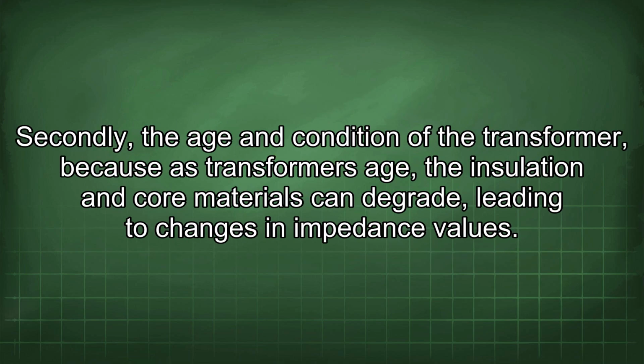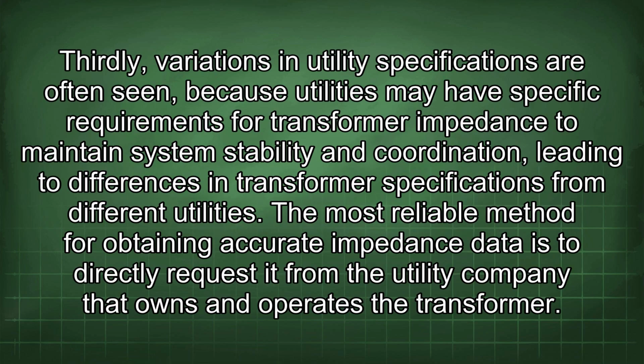Secondly, the age and condition of the transformer, because as transformers age, the insulation and core materials can degrade, leading to changes in impedance values. Thirdly, variations in utility specifications are often seen, because utilities may have specific requirements for transformer impedance to maintain system stability and coordination, leading to differences in transformer specifications from different utilities. The most reliable method for obtaining accurate impedance data is to directly request it from the utility company that owns and operates the transformer.